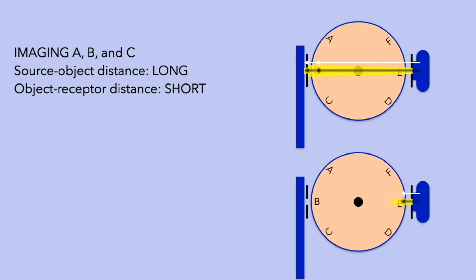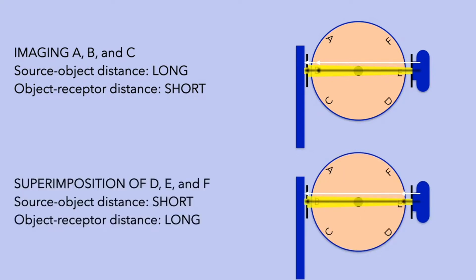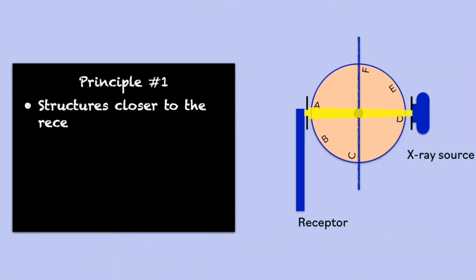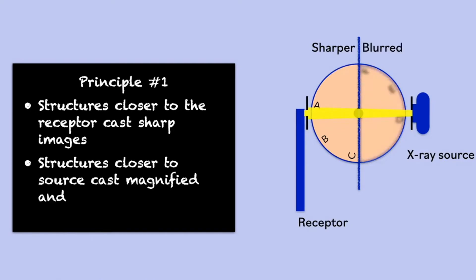In contrast, note that when structures D, E, and F pass through the beam, the source-object distance is short and the object-receptor distance is long. This makes the images of structures D, E, and F magnified and markedly unsharp. So principle number one of panoramic imaging: structures closer to the receptor cast sharp images, whereas structures closer to the source cast magnified and blurred images.